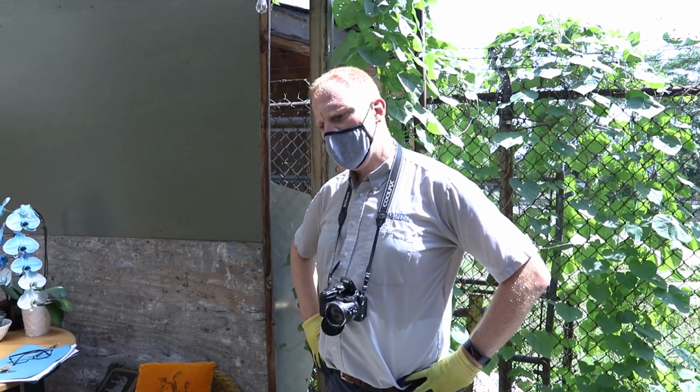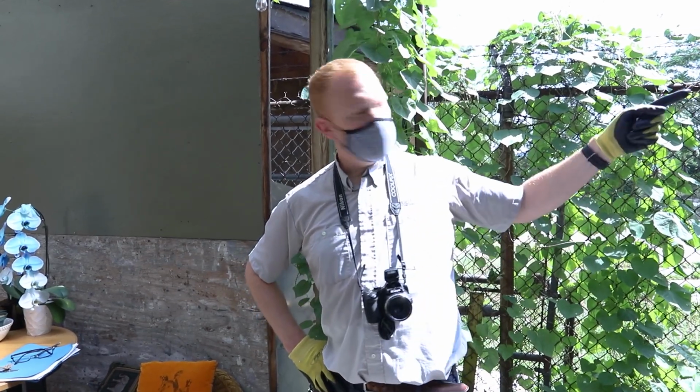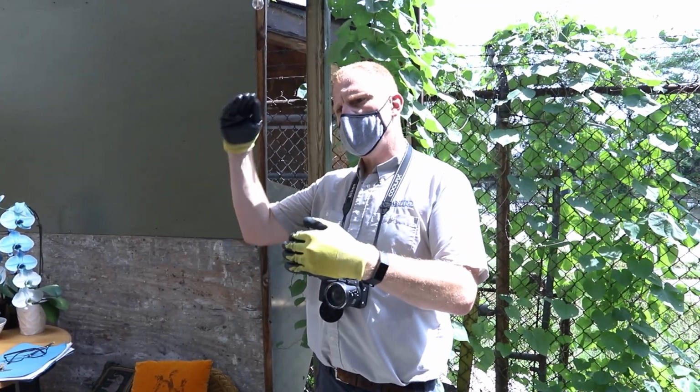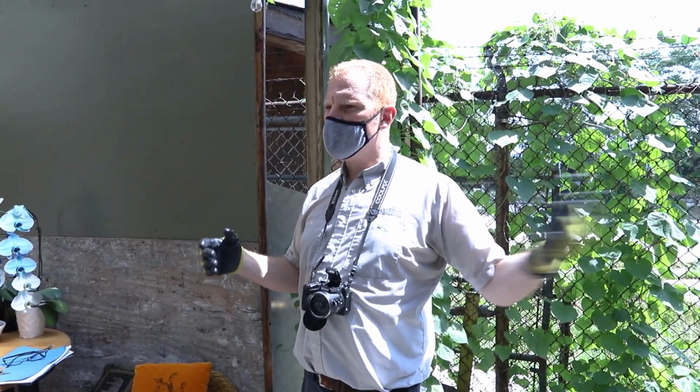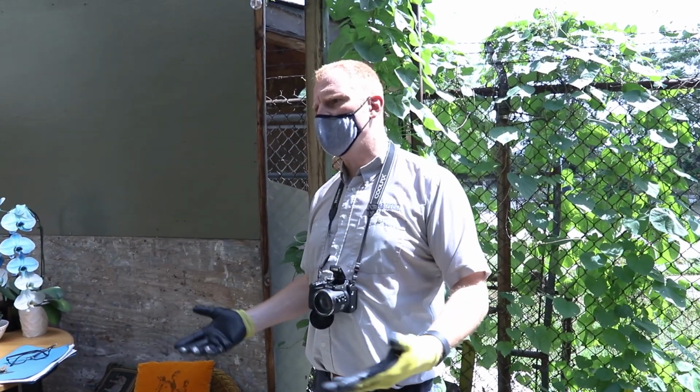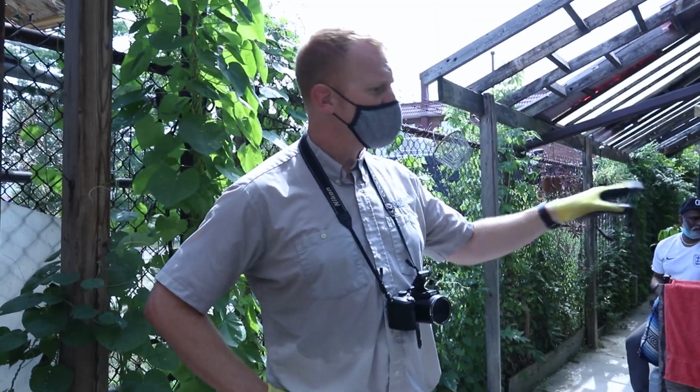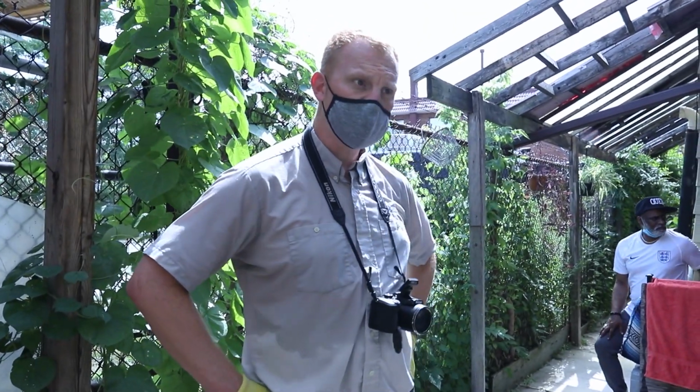Water pressure seemed okay. You do have a 100 amp service to the building. So it's not a lot of capacity spread over 3 units, but they have the gas ranges, so we're offsetting a 40 amp load on every unit. So 100 amps is probably going to work okay. A few handrails going up and down the stairs would be a good safety installation.